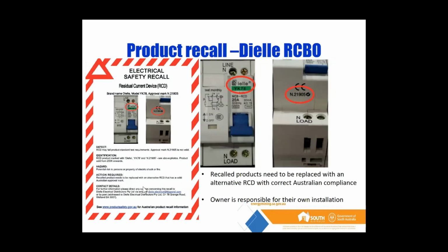So the first cab off the rank in this presentation is a recent recall that we've undergone on Dielle RCBOs. Now there were a few issues with these, and it was brought to the OTR's attention that some of these RCBOs weren't operating correctly. So after further investigation, we found that there were some issues with the certification of these products. They weren't properly certified. And we also ourselves performed some tests in a laboratory and found that these RCBOs weren't compliant in a number of ways. So really what we're trying to tell the industry is you don't have to be Superman and go and replace these every time you see them.